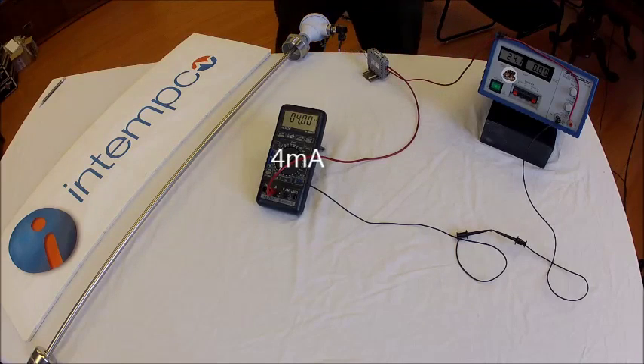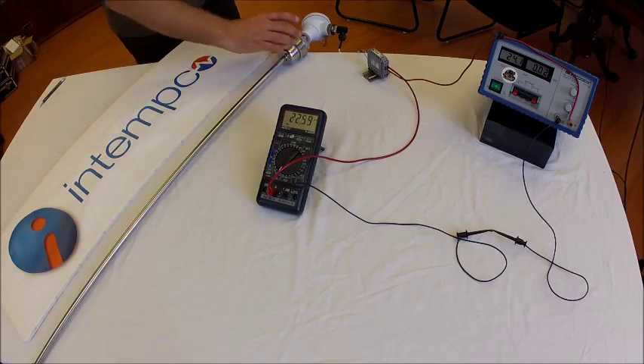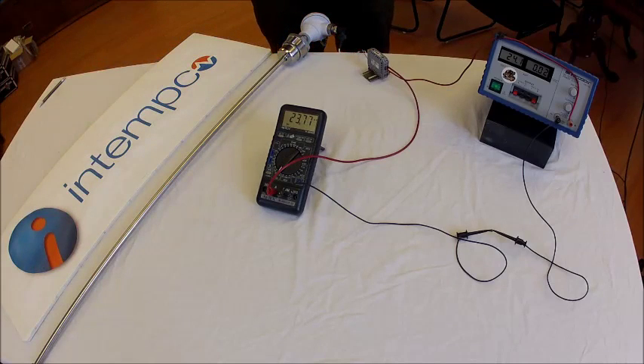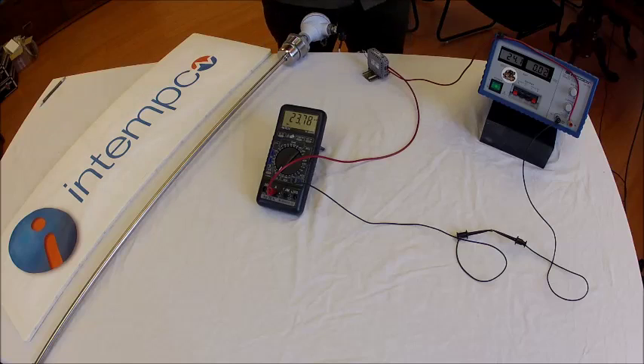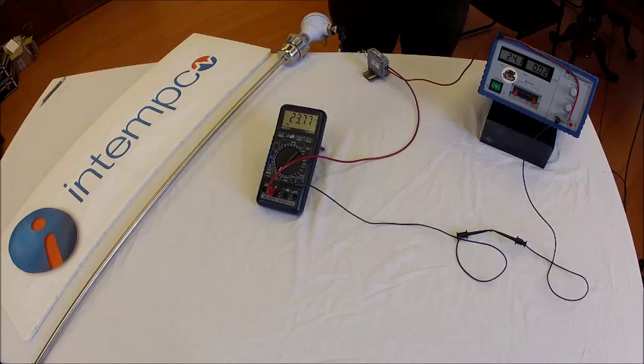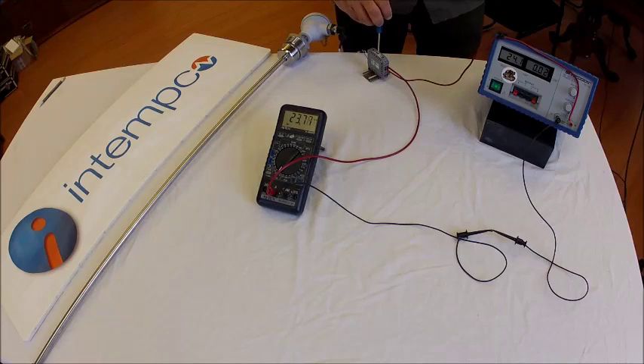If we move the float to the top position, you can see that the current changes almost to 20 milliamps. We can adjust the top point by adjusting the trim pot marked S. Observe the change on the ammeter as we make the adjustment.